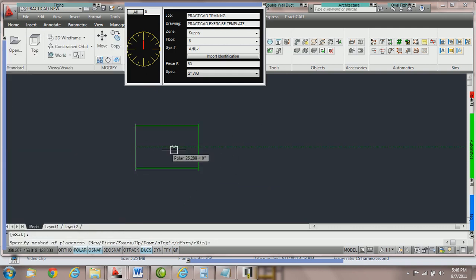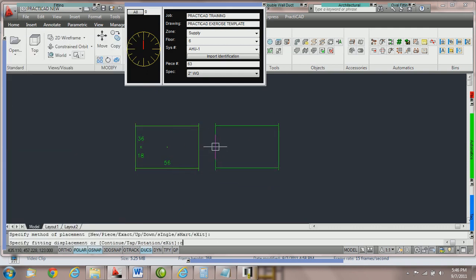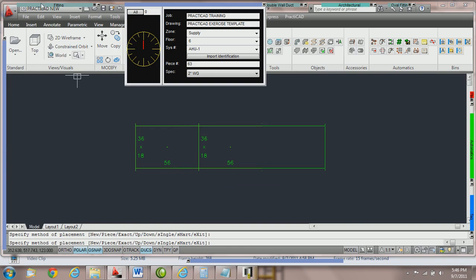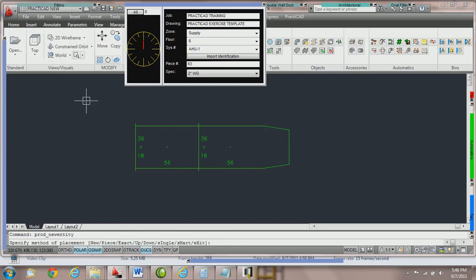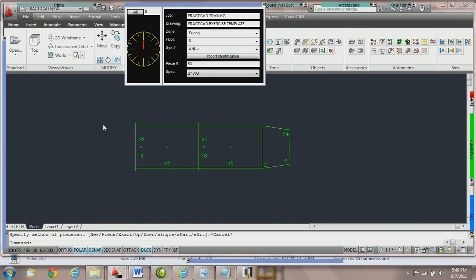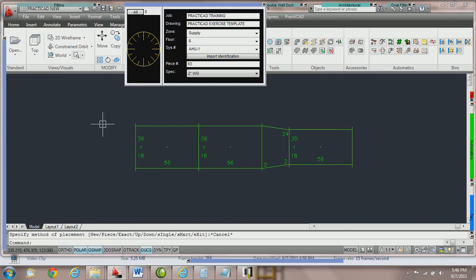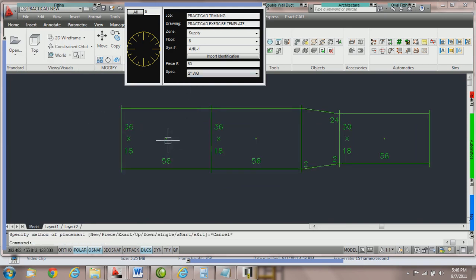We're going to put a couple of fittings on the drawing. Here we'll do two pieces of rectangular duct, a transition, and then one more piece of rectangular duct. You can see that the two inch water gauge is represented by tie rods and TDC or TDF flanges.